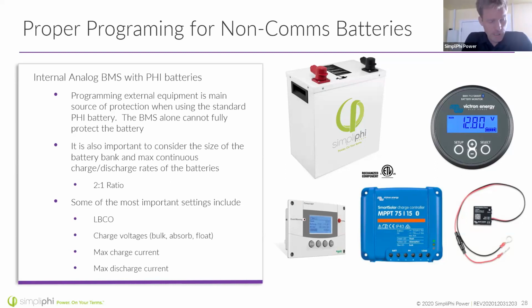Just to point out the big difference, if you cycle it down 90%, which is 49.6, I believe, if you cycle it down to an LBCO of 90%, you get about 5,000 cycles. That's more like 15 years. And if you cycle it every time down to 0%, we're expecting closer to 3,000 cycles. Now, we know that there's going to be a large variation of those cycle depths, and you won't always cycle it down to 0, but if you did, those are the number of cycles we would expect. So we do recommend that you use a 50.1 LBCO, but you can go all the way down to 48, and the warranty for 15 years is there no matter what. The voltages, we recommend looking up the appropriate bulk, absorb, and float voltages.